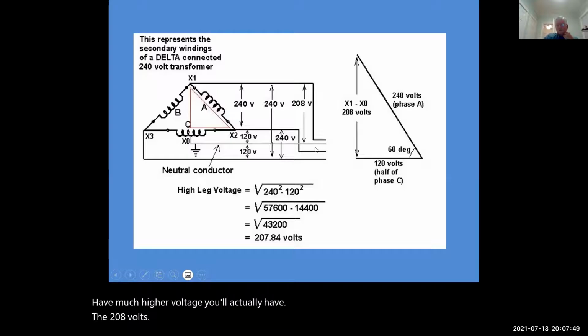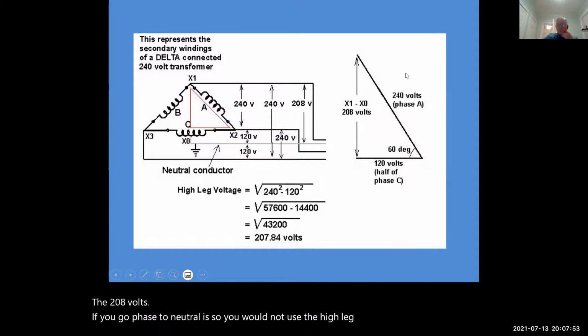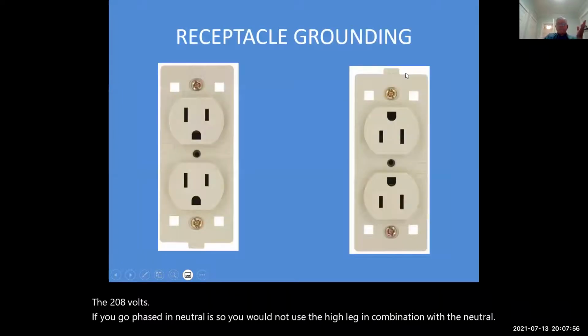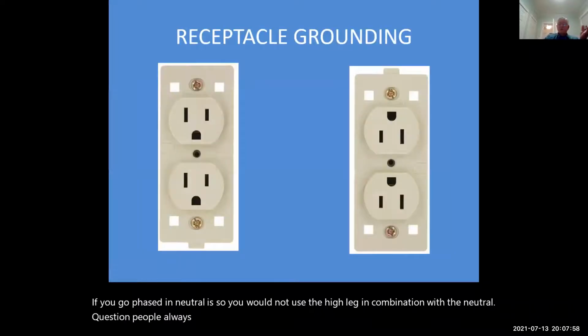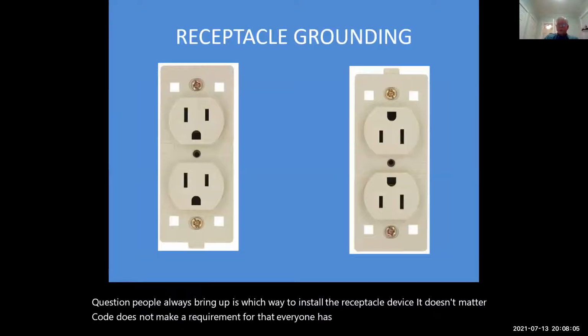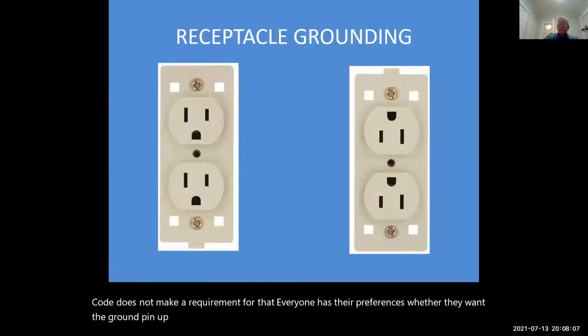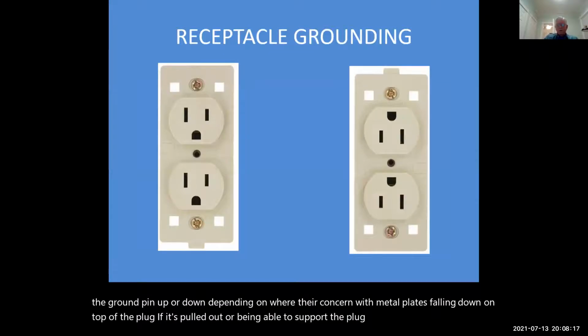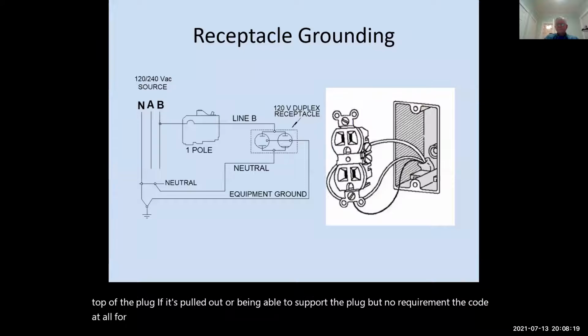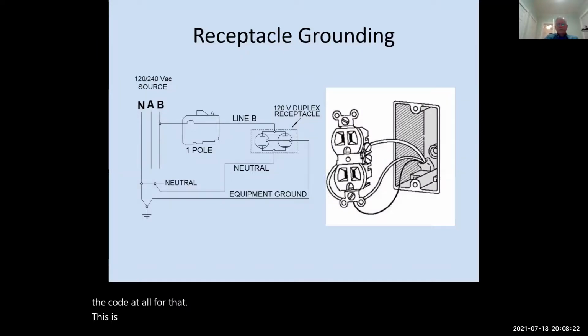You go phase to neutral there, so you would not use the high leg in combination with the neutral. The question people always bring up is which way to install the receptacle device. It doesn't matter. Code does not make a requirement for that. Everyone has their preferences, whether they want the ground pin up or down, depending on whether they're concerned with metal plates falling down on top of the plug if it's pulled out, or being able to support the plug. No requirement in the code at all for that. This is your typical house wiring.